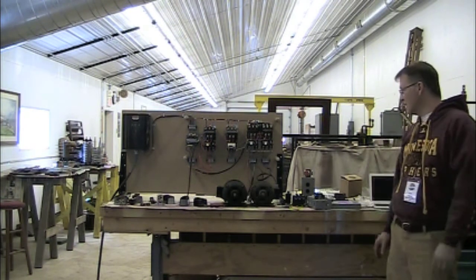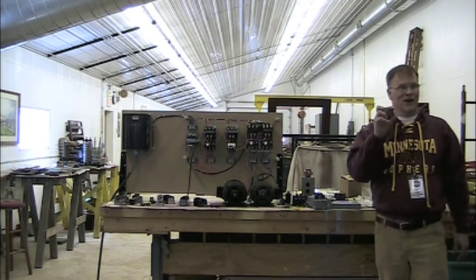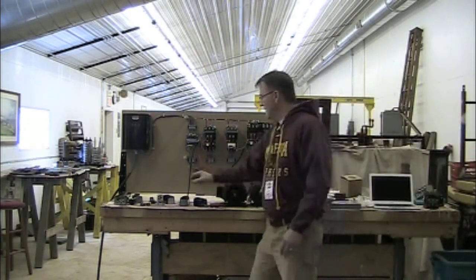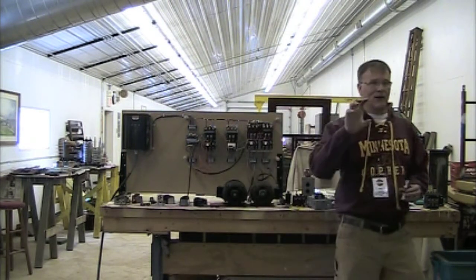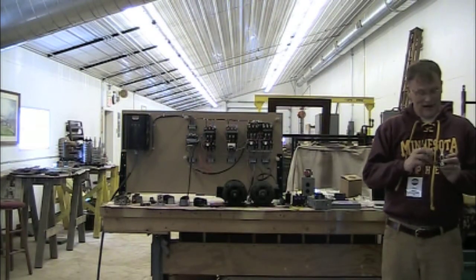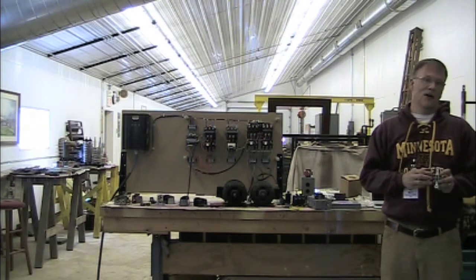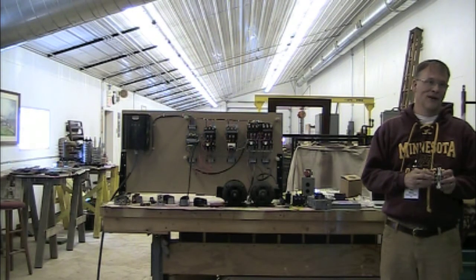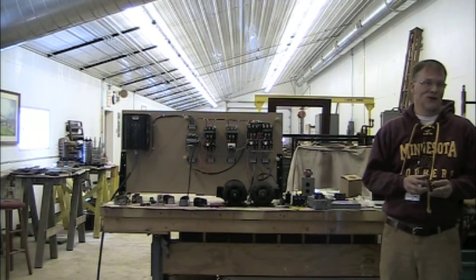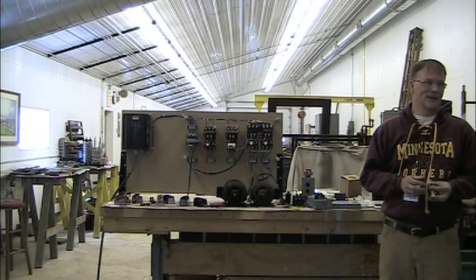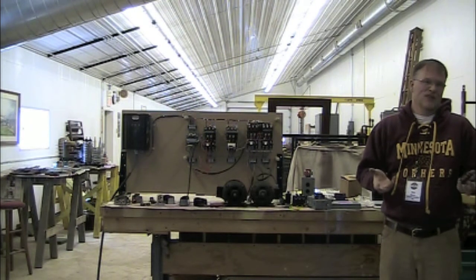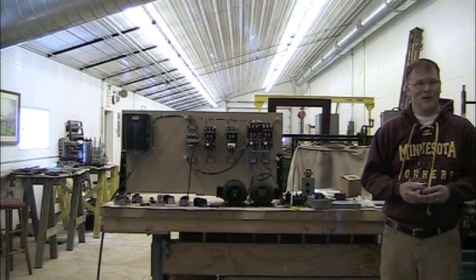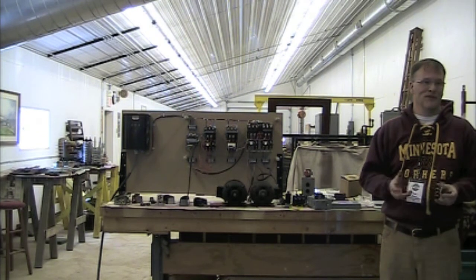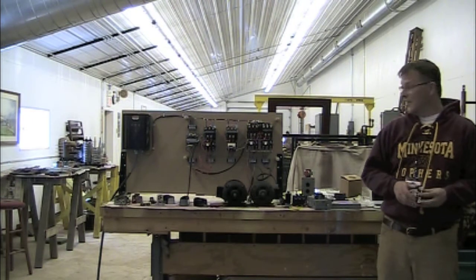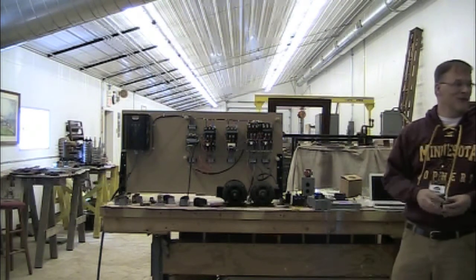And the worst ones are the little manual starters that look very similar to this, the little Arrow-Harts and Trumbulls and things like that. A lot of them actually have heater elements in them. Those are almost impossible to find a replacement heater for. So if it has a value that works for you, that's great, but finding one to actually fit the rating on your motor, and if you don't match it to the motor, why bother with putting a starter on? It's there for a purpose. It protects your motor well. That's your motor's best friend, having the proper overload set up on it.